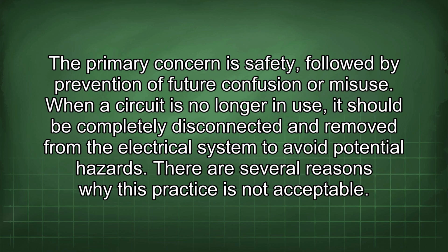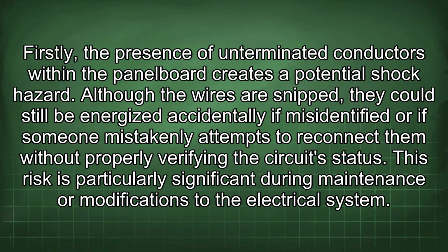When a circuit is no longer in use, it should be completely disconnected and removed from the electrical system to avoid potential hazards. There are several reasons why this practice is not acceptable. Firstly, the presence of unterminated conductors within the panel board creates a potential shock hazard. Although the wires are snipped, they could still be energized accidentally if misidentified or if someone mistakenly attempts to reconnect them without properly verifying the circuit status. This risk is particularly significant during maintenance or modifications to the electrical system.